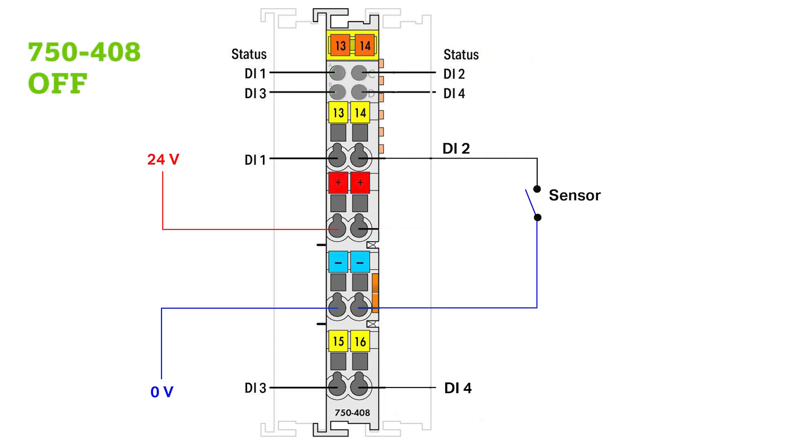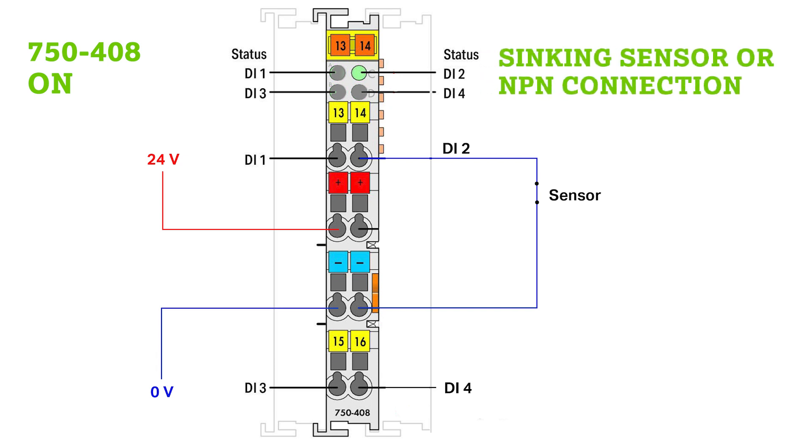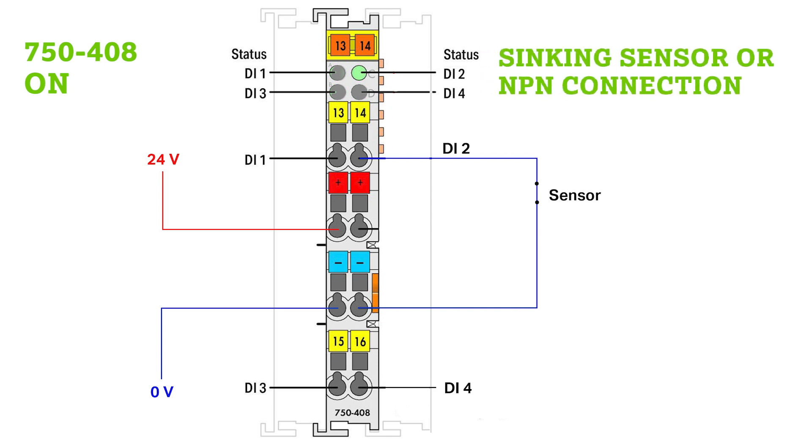WAGO's low side switching input module, the 750-408, is expecting a 0V signal at the input to be considered an ON value. That 0V can be sourced directly from the module. Here your sensor would be considered a sinking sensor or an NPN connection.